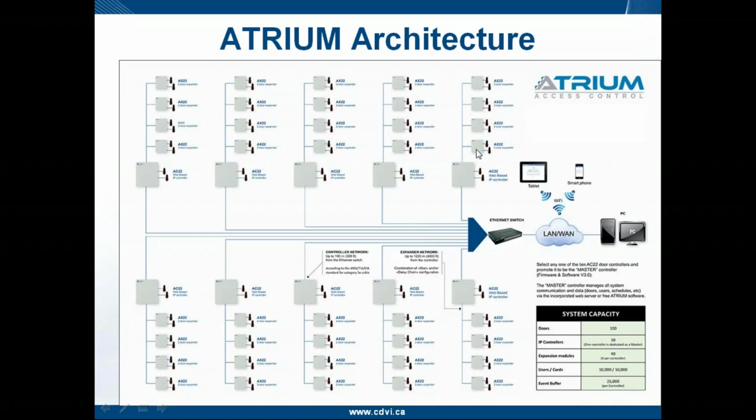There are no access levels on the expanders. There are no event buffers on the expanders. So step one, once the expander goes offline, we secure the door. We lock both doors on that expander. Now, the 500 cards that were granted access previous to the failure will continue functioning.